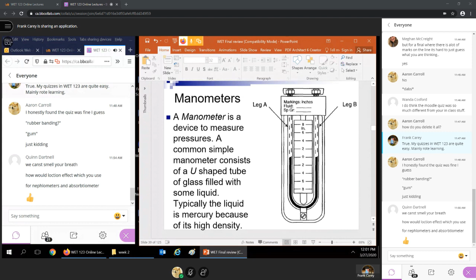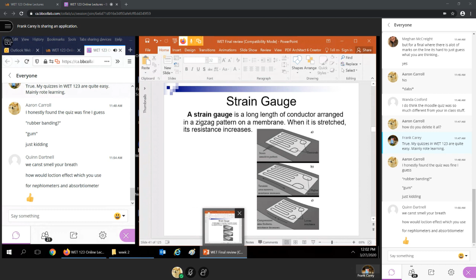So there are three methods for pressure measurement, and they are piezoelectric, strain gauge, and capacitive sensors. By far, the most common are piezoelectric, so you'll find them in generally most pressure gauges, but there are some that also have strain gauges or capacitive gauges. So you should know all three and how they work.